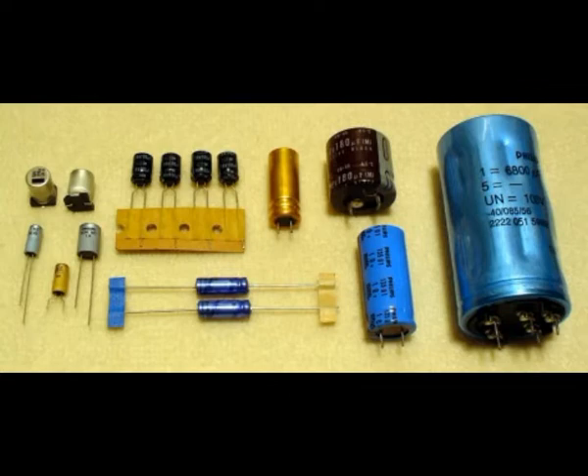For capacitors with a rated voltage of 315 volts, the surge voltage is 1.15 times the rated voltage, and for capacitors with a rated voltage exceeding 315 volts, the surge voltage is 1.10 times the rated voltage.